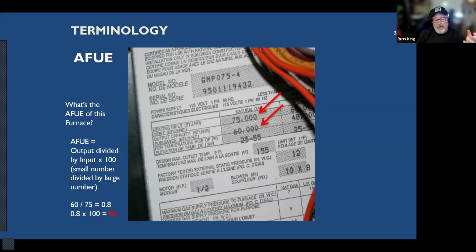And so what happens when you do that is, when you burn gas, it gives off what we call combustion products, including carbon monoxide, but including carbon dioxide, and a lot of water vapor comes from natural gas when you burn it. And so when you take those hot combustion products and run them back through another heat exchanger and blow cool air across it to cool them, the water condenses out of it. The water droplets condense out, and we call that a condensing furnace.